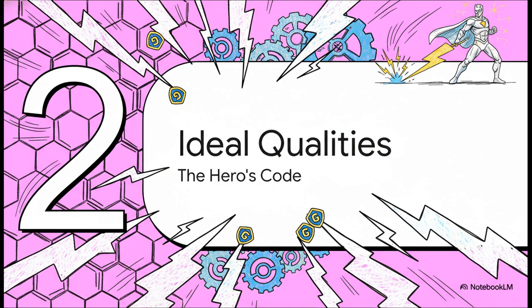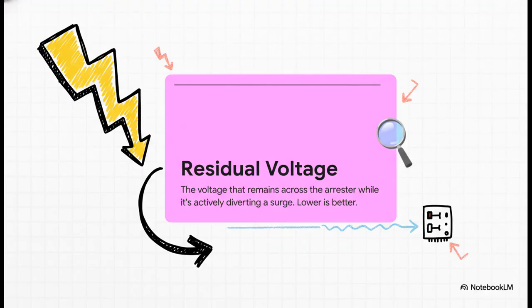But look, to pull off this high-speed, high-stakes job over and over again, an arrestor needs a very specific set of skills. This isn't just a simple switch we're talking about. It has to be a seriously refined and reliable piece of tech. Okay, first up, and this one is absolutely key, is a concept called residual voltage. Now, this isn't the voltage from the lightning itself. This is the little bit of leftover voltage that actually gets past the arrestor and reaches the equipment while the arrestor is busy diverting that main surge.